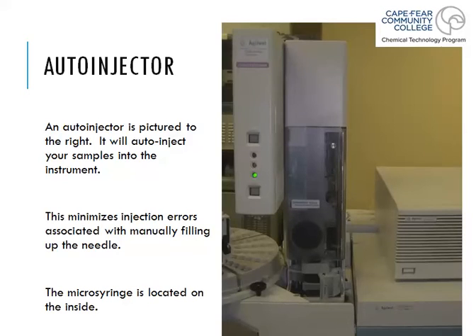Here's a close-up picture of an auto-injector with a wheel injector to the side that can probably hold 70 or more samples. It rotates, loads up a vial, the syringe pulls the sample up, moves the vial back to its spot, and squirts the sample into the machine through the injector port. That's where this video stops, and in the next video we're going to talk about another piece of the injector port called the glass insert.